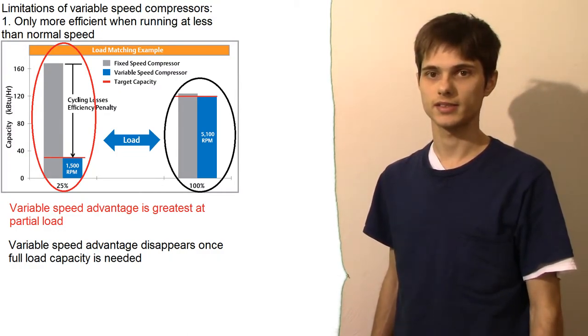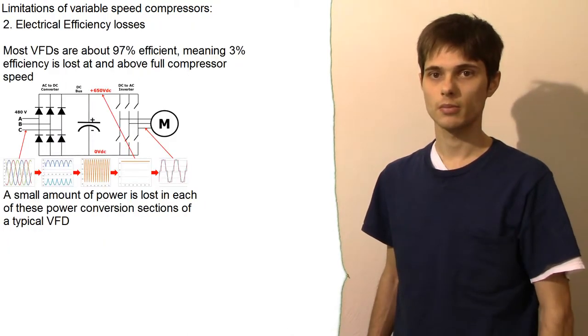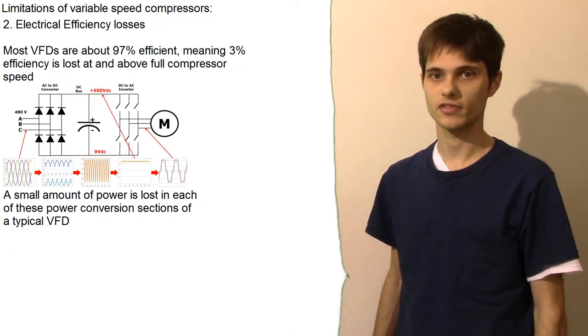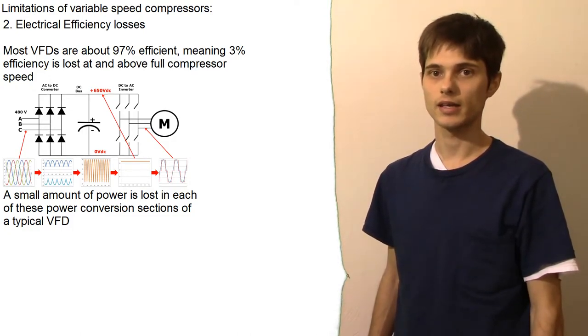Sometimes more capacity is needed and that's where the efficiency falls. This is not only because the speed of the compression is higher, you have more friction, more losses, but also because the variable frequency drive and the electronics itself at this point consume more energy and not less.